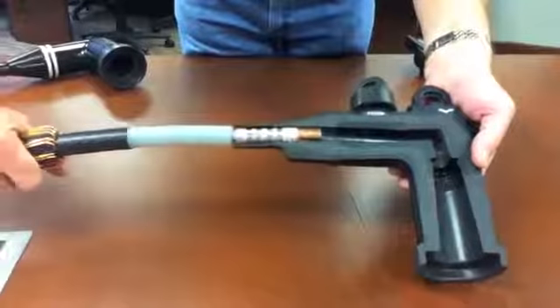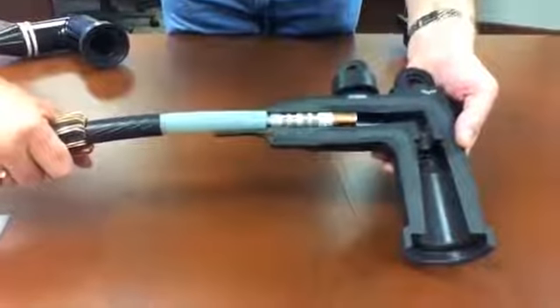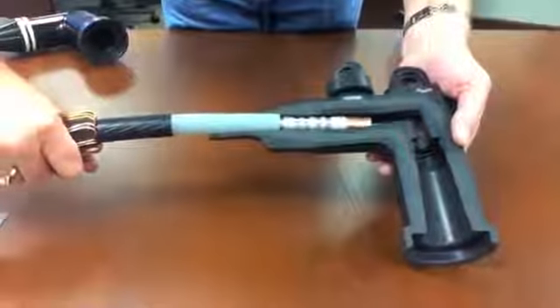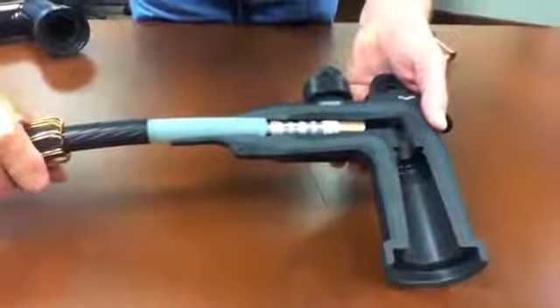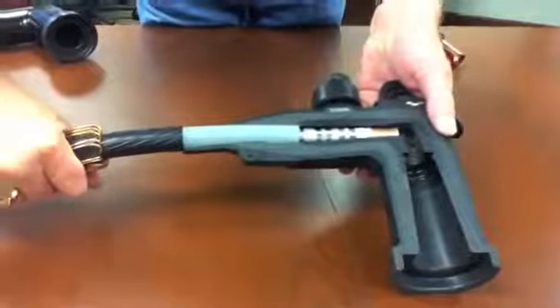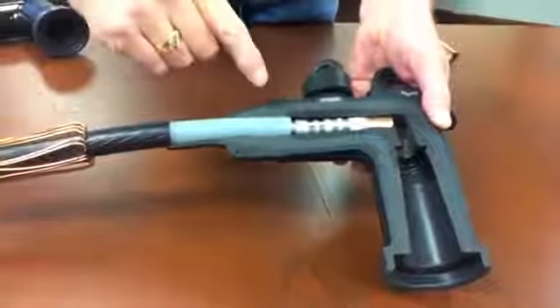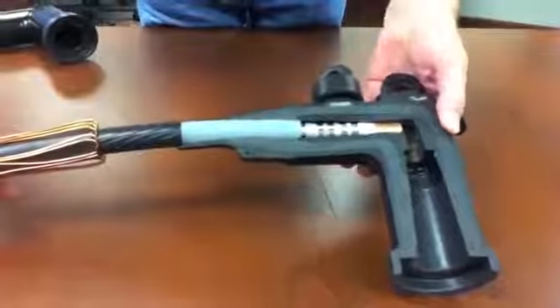I've prepared a cable. I've crimped a lug on and stripped it down according to directions, but what I haven't done is beveled the edge of the insulation. The installation instructions say to lubricate this with a thin film over the entire surface and also to lubricate the bore of the elbow. As the cable is inserted into the housing, you're going to meet with some resistance as the insulation of the cable is pushed further into the housing, and then you will meet more resistance as the insulation meets the conductive insert of the housing.